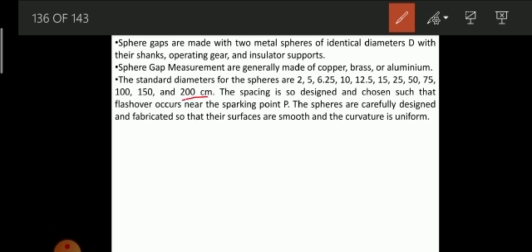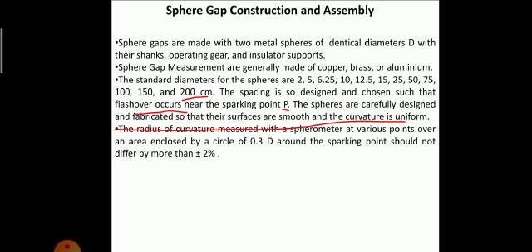The spacing is so designed and chosen that the flashovers occur near the sparking potential. The spheres are carefully designed and fabricated so that their surfaces are smooth and the curvature is uniform. The radius of curvature is measured with a spherometer at various points over an area enclosed by a circle of 0.3d around the sparking point, and should not differ by more than plus or minus 2% of the nominal value.